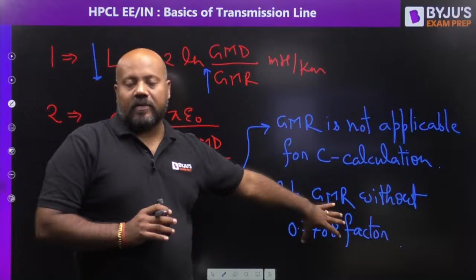What is that slight difference? This R is going to be like GMR without 0.7788 factor. I hope you know this. When we are calculating the GMR, we are using this factor in case of inductance calculation. When you are doing the same calculation for the capacitance, the only thing you have to do is just remove this factor of 0.7788 and rest of the procedure is same. But because we understand that GMR is not going to be applicable as a concept in case of capacitance calculation, we are simply writing this as R.